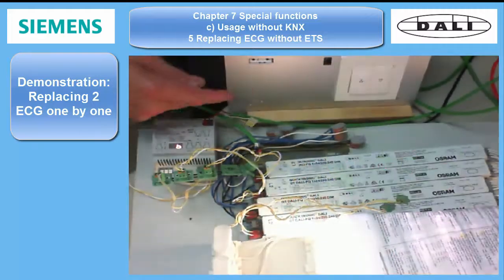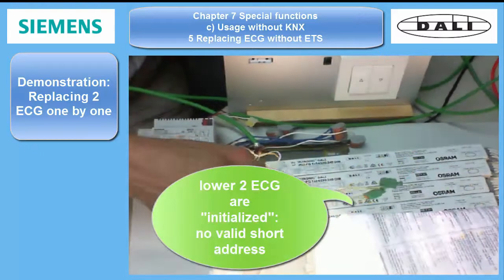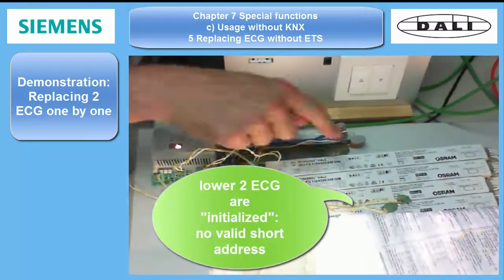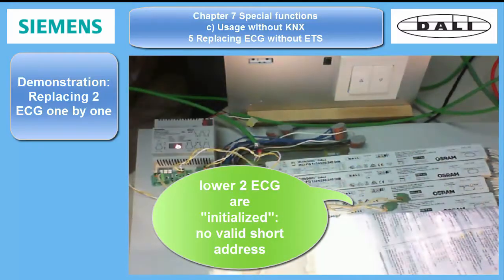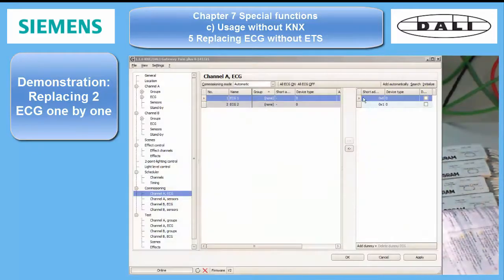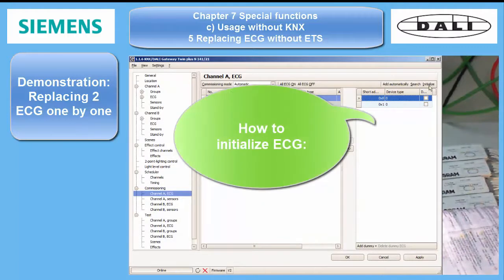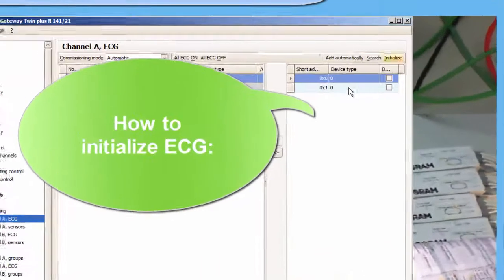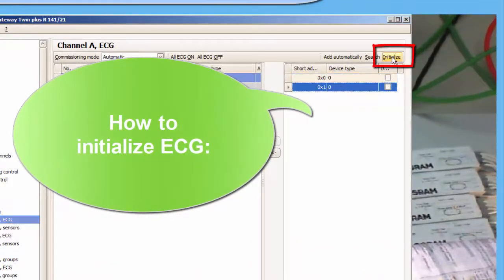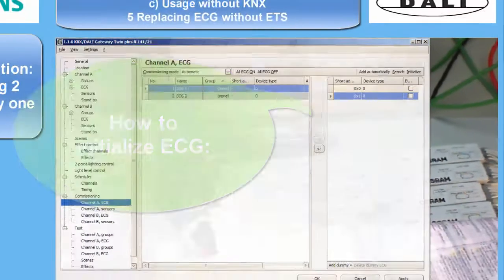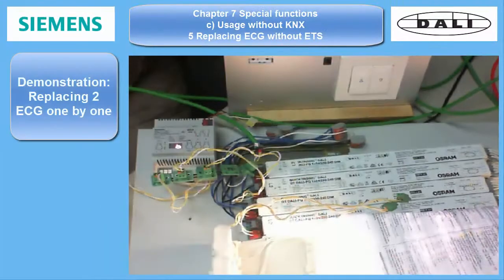The lower two ECG are initialized. That means they don't have a valid short address. This condition can be achieved in the commissioning dialog of the DALI gateway after a bus ECG scan. The ECG must be selected and the button initialize be pressed.